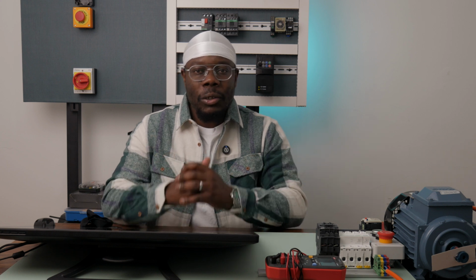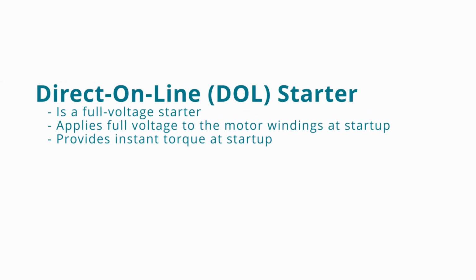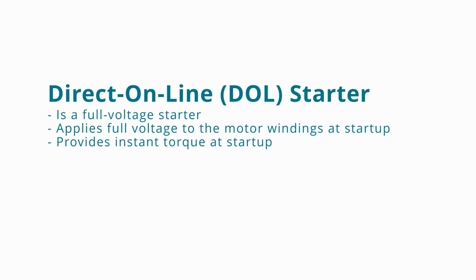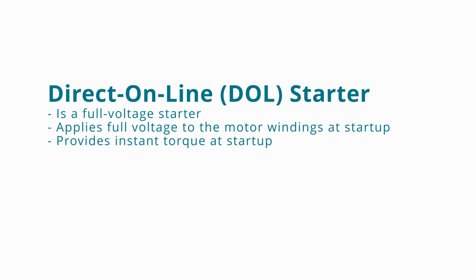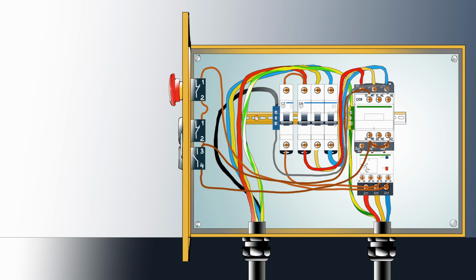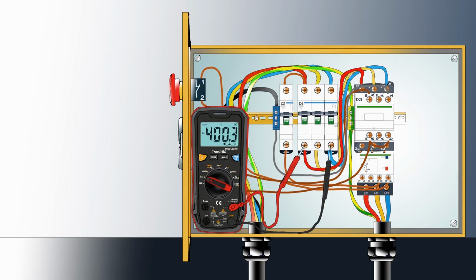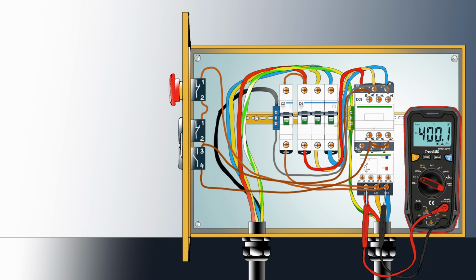Now, the first thing that we're going to do is to define what a direct-on-line motor starter is. A direct-on-line motor starter is a full voltage starter. It applies the full voltage to the motor windings at startup, providing instant torque. For example, if a motor is connected to a 3-phase 400-volt supply, the starter will apply the full line voltage of 400 volts to the motor.